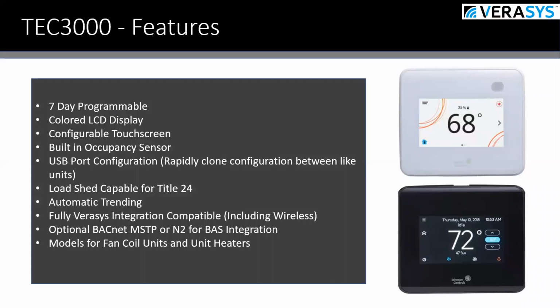The TEC 3000 is really one of the key technologies that fulfills the requirement for these ASHRAE pandemic-condition codes, and they're very popular. These can be set up wired or wireless. They're programmable, have a built-in occupancy sensor, a USB port for quick configuration, and embedded trending. They can also be integrated with not only BACnet MSTP but also an N2 bus for other building automation integration.